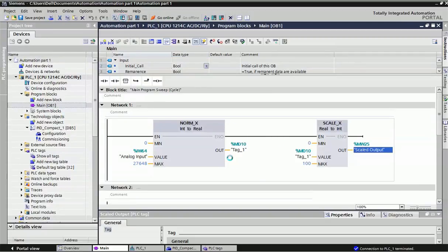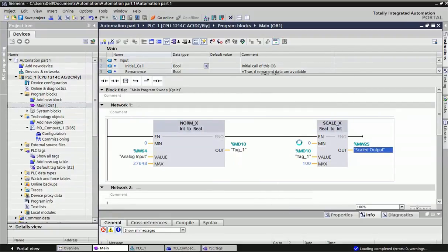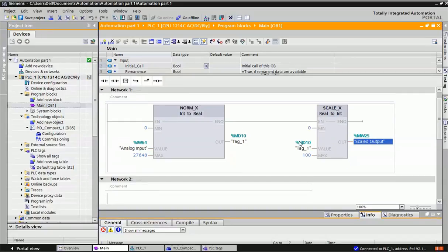Here you can see this analog value is changing according to the input. Linearly, the scaling output will change. The standard range is 4 to 20 milliampere. Here I have used the voltage port, so I am giving plus or minus 10 voltage. Here exactly we are not getting plus 10 voltage, so that's why it will vary from 27,648 - it is going beyond limit. That's why I am not getting exactly the scaled output here.